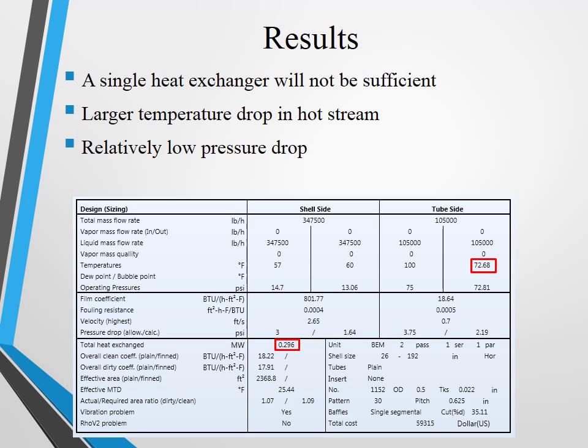Through an iteration process, the following results were obtained. With this heat exchanger design only transferring 0.296 megawatts of heat, a total of 4 heat exchangers would be needed to fulfill the 1 megawatt HPC output. A propylene glycol flow rate of 105,000 pounds per hour was able to produce an exchanger that was slightly under 20 feet and provided delta T of 27 degrees Fahrenheit for the hot stream coming from the HPC. This allows the propylene glycol to be cycled back through the HPC and absorb a significant amount of heat due to the high delta T potential. This was done all with a delta T of the cold stream of 3 degrees Fahrenheit. The pressure drops were kept relatively low at 11.1% in the shell side and 2.9% in the tube side.